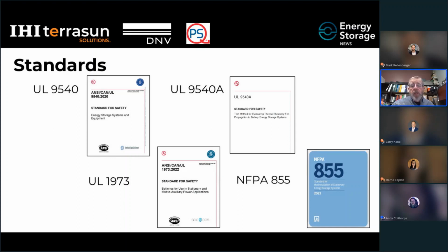NFPA 855 is not recognized by authorities having jurisdiction in Canada. In Canada, you would rely on the rules in the Canadian Electrical Code, Section 64. In the US, in addition to NFPA 855, you'd have the requirements in Article 706 of the National Electrical Code.